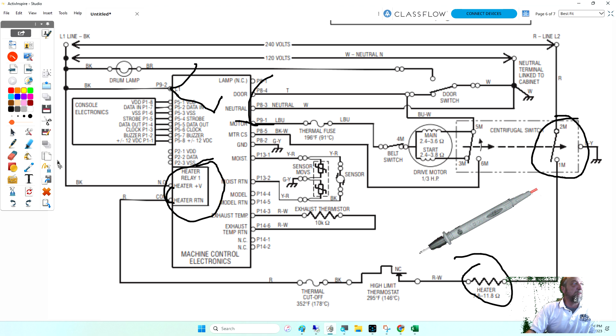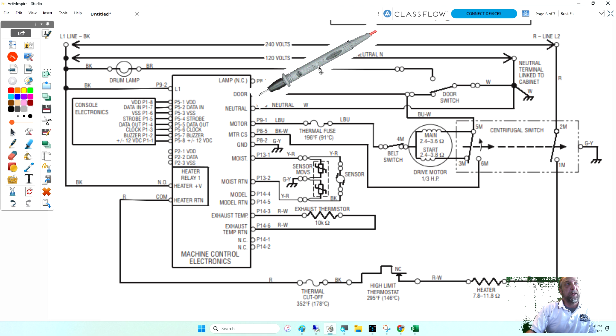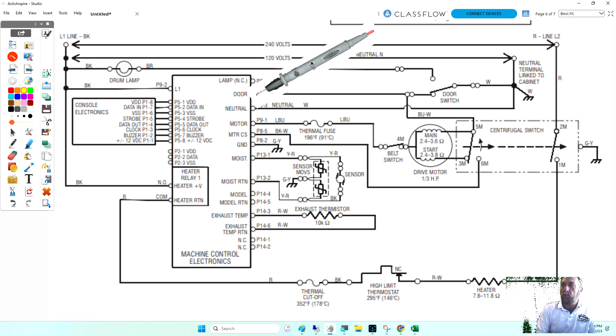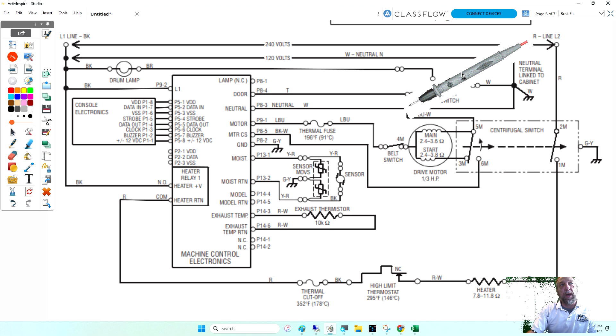So going back to the importance of troubleshooting with voltage: we check one side of the load and the other side of the load. This is the line side of the motor and this is the neutral side, and we only move one meter lead if we do not have voltage. We move it back to find the voltage, or here on P91, we go back and find the voltage. If I don't have voltage here and I have voltage there, what's my problem?